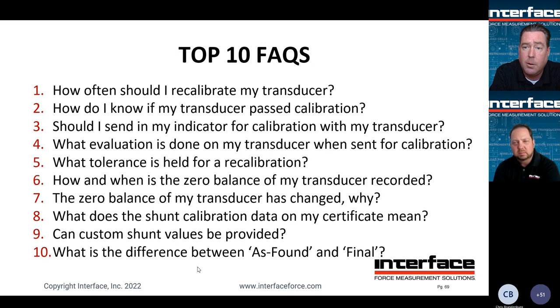That shunt data is essentially we apply a resistor across multiple legs of the bridge, and it's electrically simulating an applied load using a known resistor value. This is a very high-end precision wire wound resistor, so very repeatable with very low TC. The end user can then use that same resistor value and apply that resistance across those same legs of the bridge and simulate the output that we got.